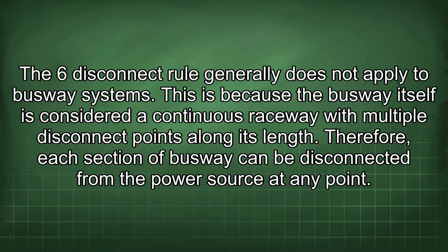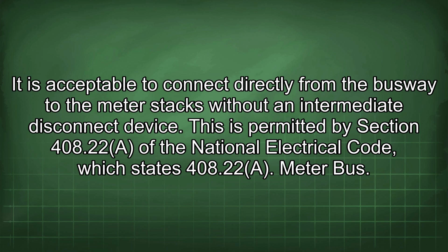The 6 disconnect rule generally does not apply to busway systems. This is because the busway itself is considered a continuous raceway with multiple disconnect points along its length. Therefore, each section of busway can be disconnected from the power source at any point. It is acceptable to connect directly from the busway to the meter stacks without an intermediate disconnect device.